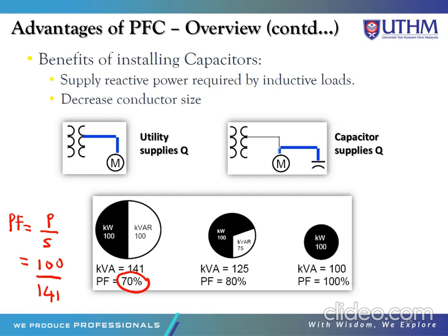The same goes for the second case. When we put in the capacitor, the kVAR can be reduced from 100 to 75, so we get a power factor of 80%, an increase from the previous case. In the last case, the kilowatt is 100 and the kVA is also 100, which means P is equal to S, so the power factor is 100%. So it shows that when we put the capacitor in parallel with the load, the power factor can be increased.